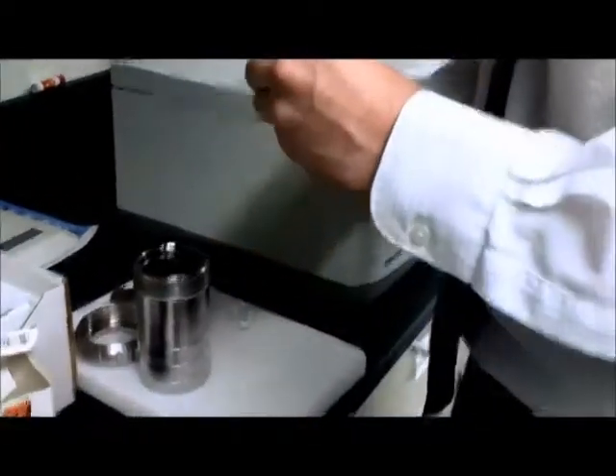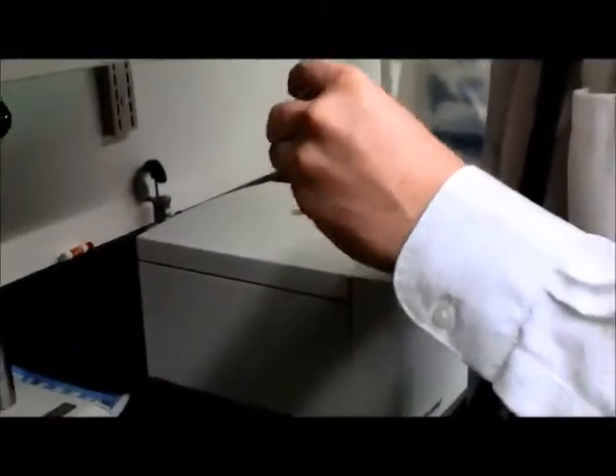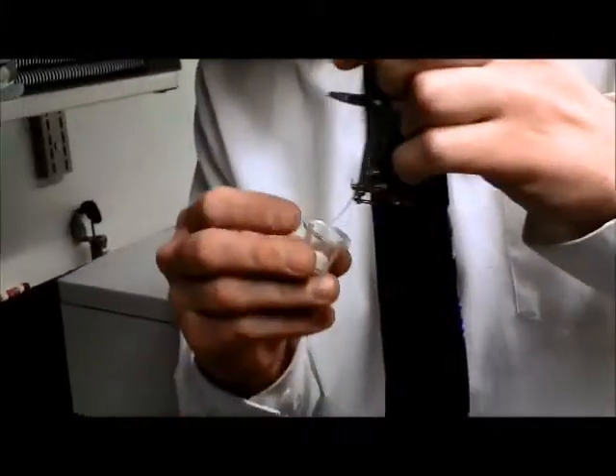So we have a little benzoic acid pellet. This is the standard we use for calibrating the machine, so we can check to see where our calibration is at. We know the heat of combustion of that sample, so we can put a definite amount of heat into the calorimeter. Correct.